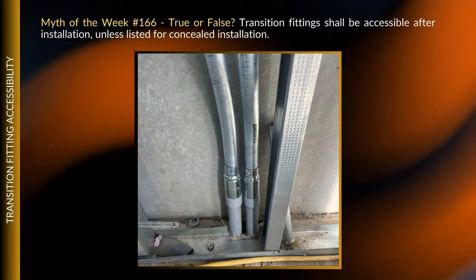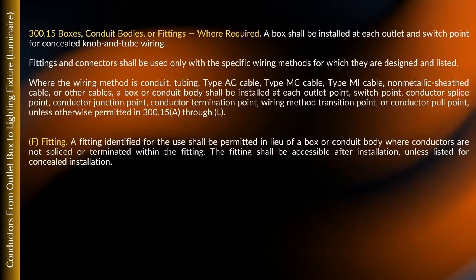Now when you go in and look at this, I put two sections here basically. What I decided is where you're really getting into it is going to be the third paragraph in 300.15, and then F is where it gets into the fitting. But what I like to point out here is they talk about where you have the wiring method, and if it's conduit, tubing, type AC cable, type MC cable, type MI cable, or your non-metallic sheathed cable or other cables, and you have a box or conduit body, it tells you it shall be installed at each outlet point, switch point, conductor splice point, conductor junction point, conductor termination point, and then this is the one here, wiring method transition point or conductor pull point, unless otherwise specified in 300.15A through L.